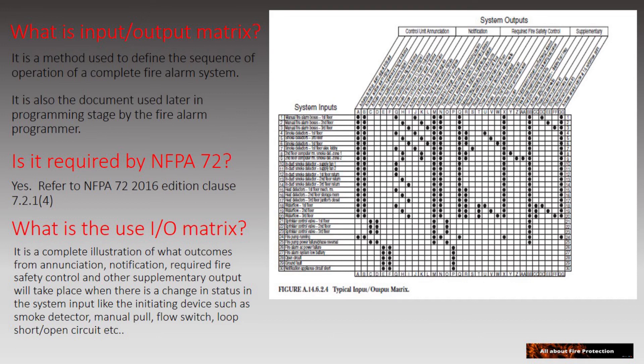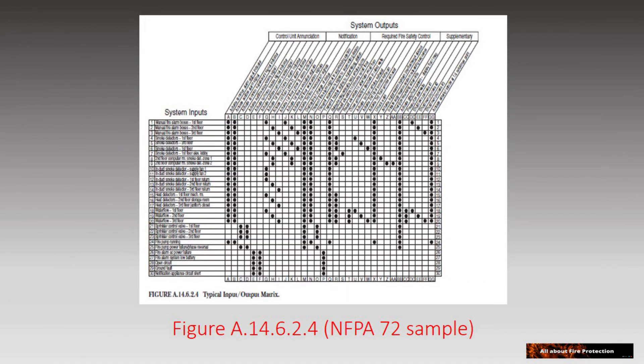The input and output matrix is used to illustrate the complete sequence of operation of a fire alarm system. As mentioned earlier, it is used as a document to be approved by the consultant for programming. Here is the figure shown in the annexure of NFPA 72 as a sample of an input and output matrix.